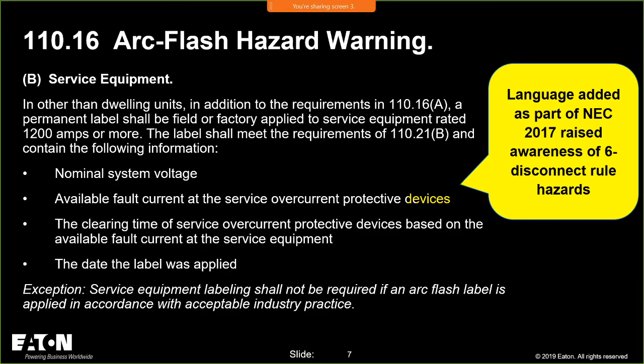All right, so that's sort of the labels associated with that. Again, I've been trying to help people understand for 110.16, which is not a 2020 cycle change, but you should be driving the arc flash label as opposed to labeling with an available fault current and a clearing time. I think the intent of 110.16b was really around the 70E table method.